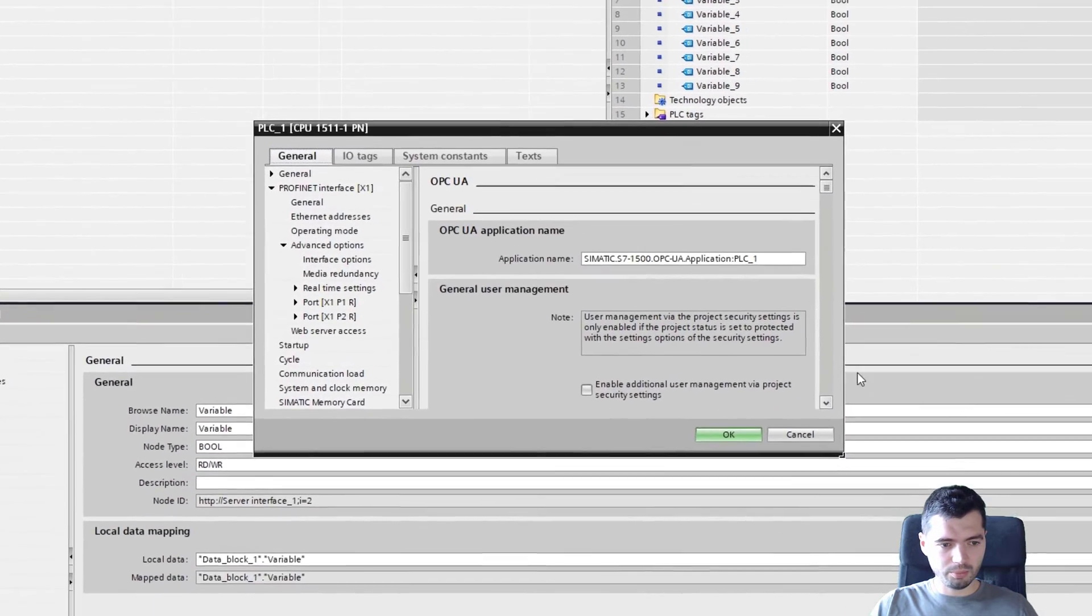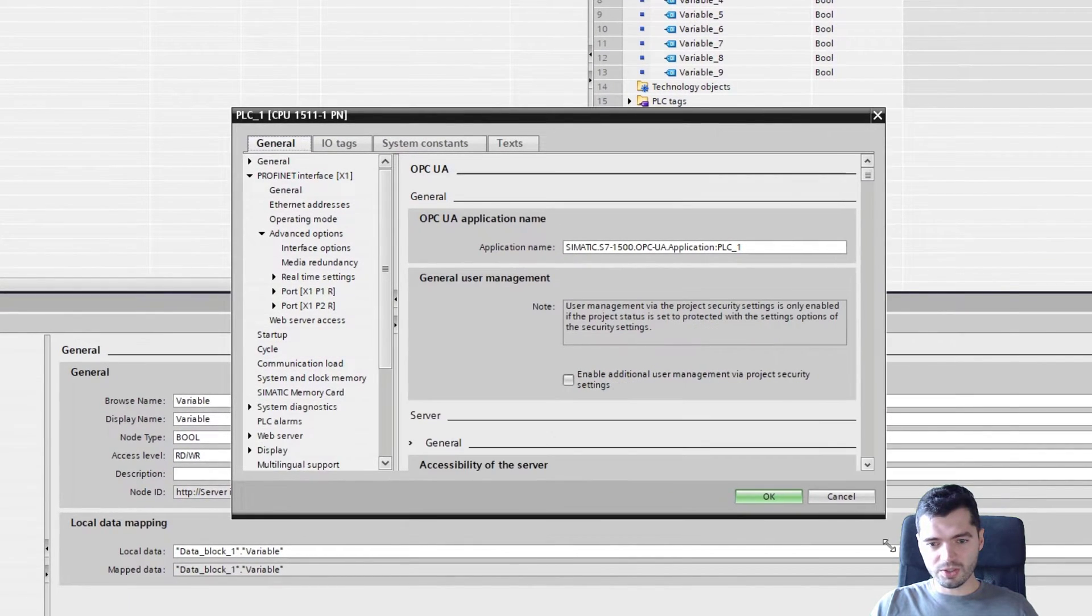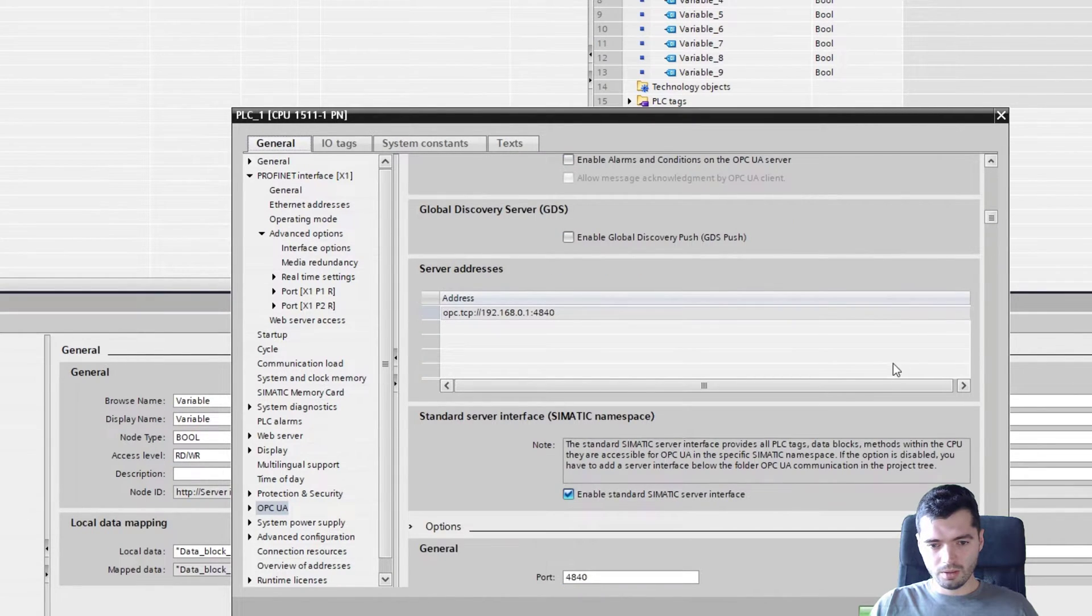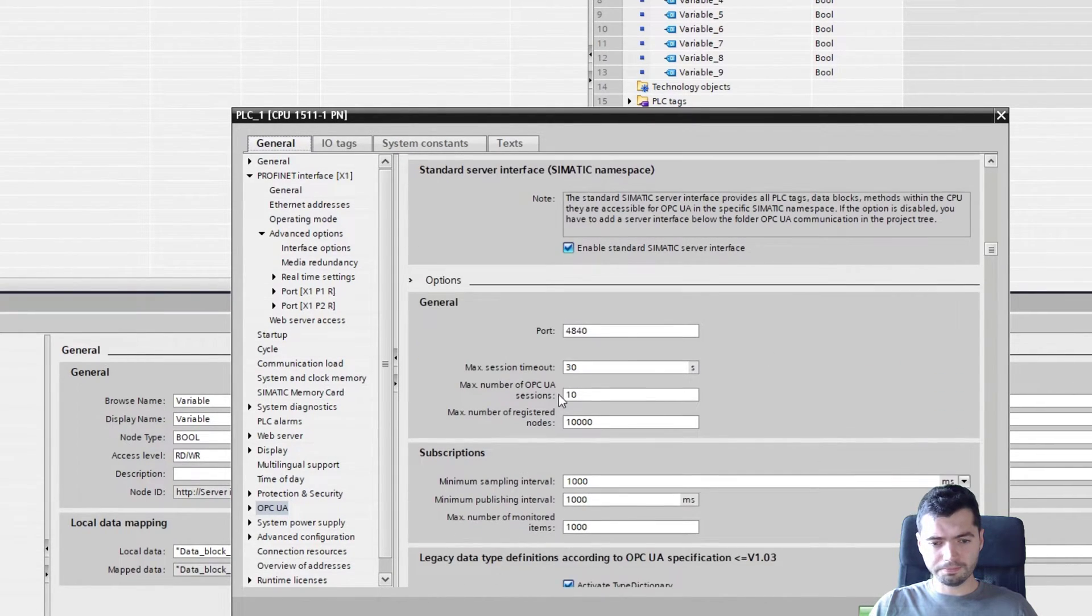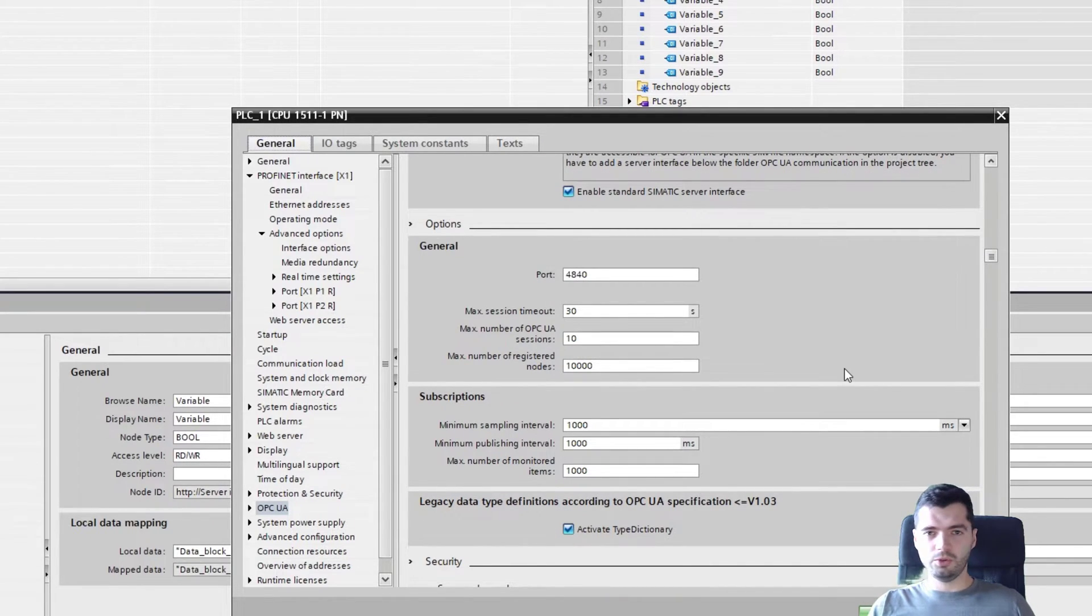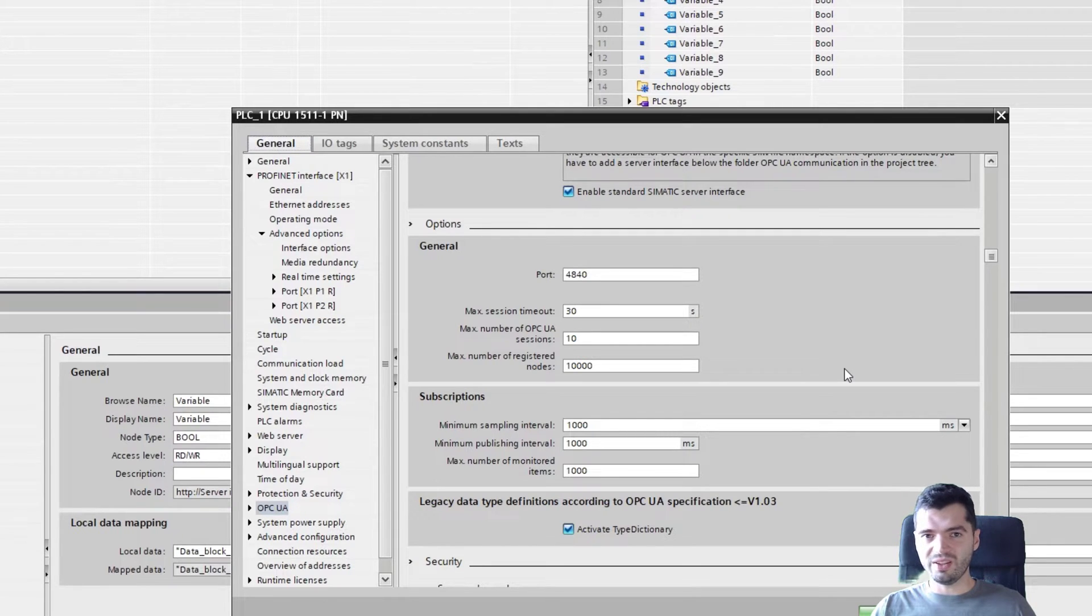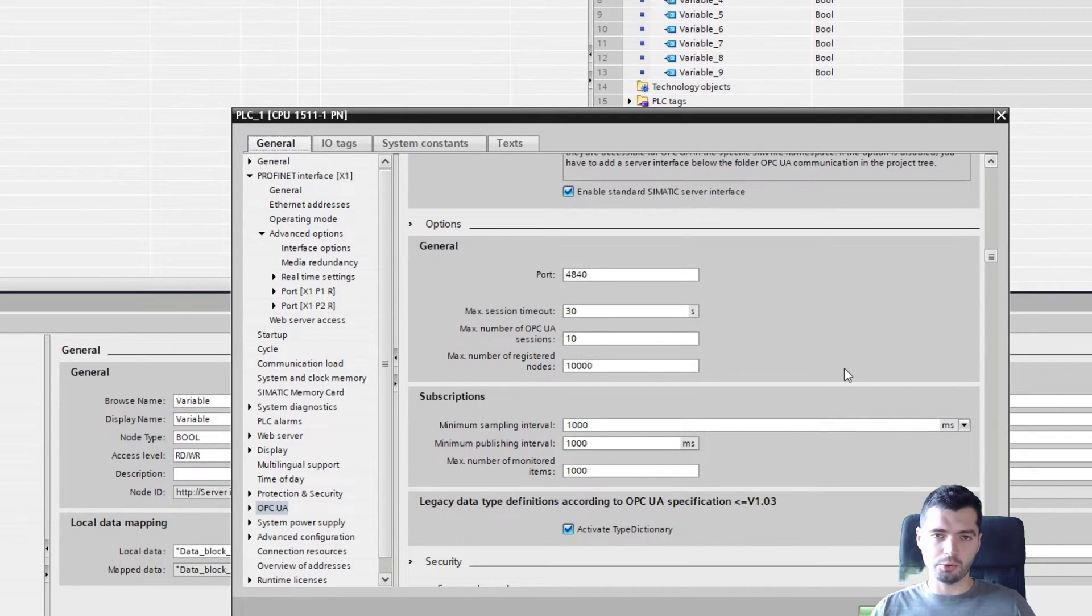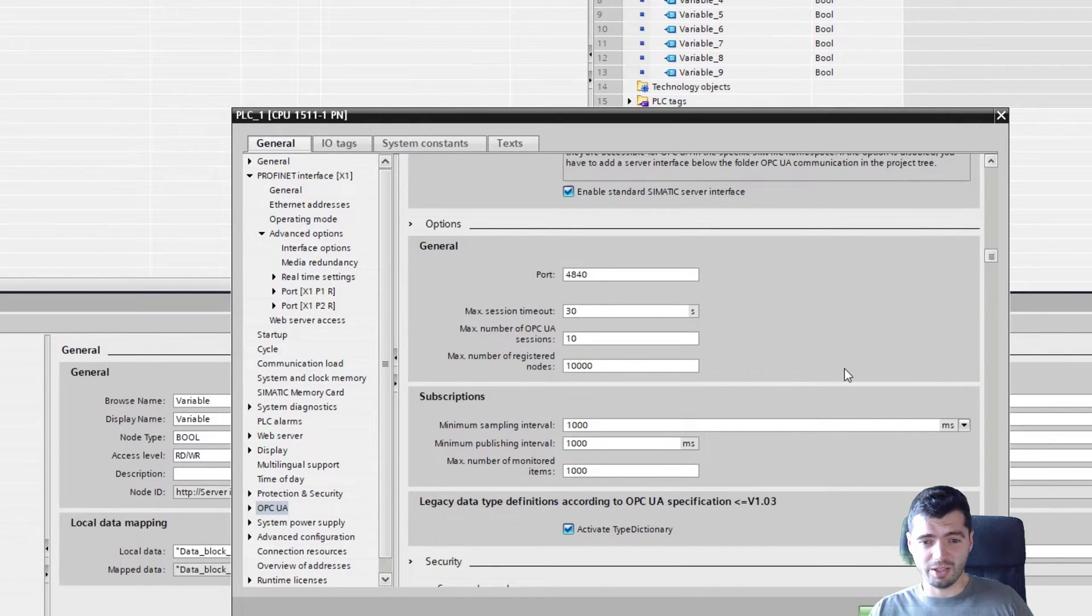Going back to the properties, what else is there of interest? It's the server interface. This is actually quite important, so the port. If you want to use any OPC UA client to connect to your OPC UA server, you will need to know the port of your OPC UA server. By default, TIA assigns 4840 to the OPC UA servers. In most situations, just leaving it is fine.